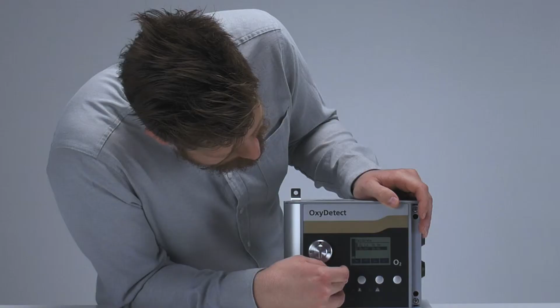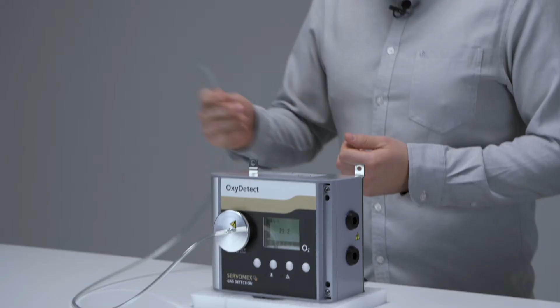The OxyDetect is powered by a 24-volt DC supply, which would be supplied from the third-party gas detection system that it is integrated into. On power up, the OxyDetect will go through a simple startup procedure, and Servomex recommend that the unit is left for around 45 minutes to stabilise and settle. After initial setup, it's recommended that the OxyDetect is calibrated. This is a very easy procedure that the user can perform, and just involves this supplied calibration piece being fitted to the front of the unit and the other end being connected to one of 2 calibration gases that are needed, nitrogen for 0 and air for span.